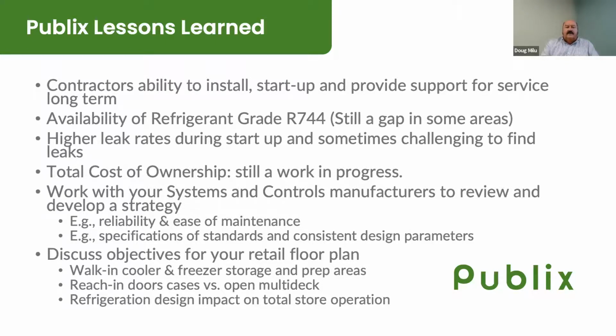One of the other lessons learned was a little bit higher leak rates during startup, and it's not through a system issue. As we're doing startup, there's construction going on - utility providers on site are transferring lines behind the store if we're in a rural area, or upgrading transformers. So usually during startup, when we're trying to either charge the system or bring everything down to temperature, the utility provider will disconnect power to the building, unbeknownst to us.